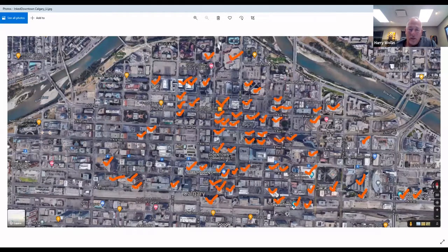I think the biggest challenge right now is what LEED has done with water consumption, where low flow fixtures have really made it difficult on the water booster line sizing and the PRVs. All the PRVs that used to be 2 and 3 inch, now you get a urinal that opens up and needs only a little squirt of water to flush. When you really think about it, the old line sizes that were there, the inch and a quarter, only took about 4 feet of water out of the system.